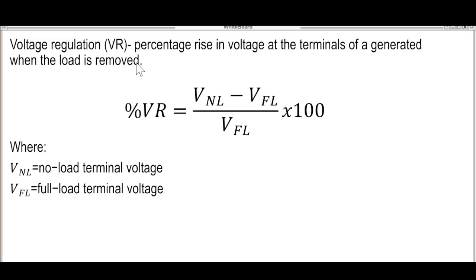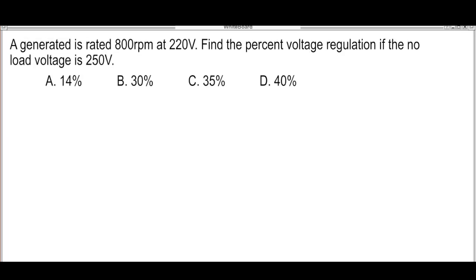Okay? So with the formula VNL, that is the no load terminal voltage minus the full load terminal voltage divided by the full load terminal voltage. So we have this example, no? Generator is rated 800 RPM at 220 volts. So find the percent voltage regulation if the no load voltage is 250. Yan. Okay. So let's solve this one, no?